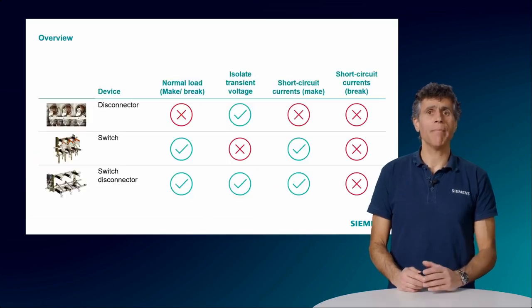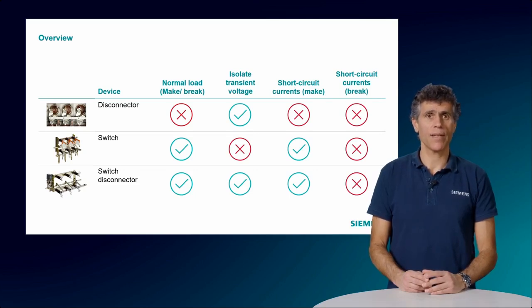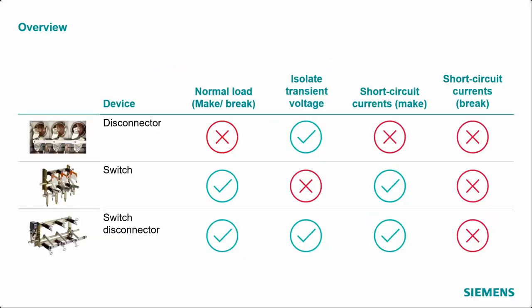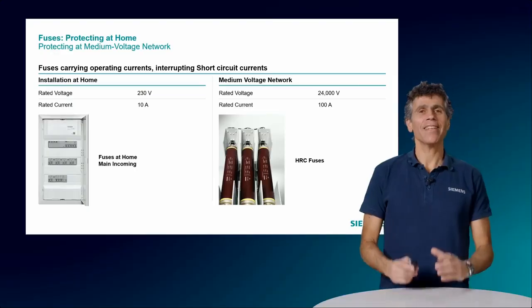And here, better than 1000 words, a short overview of the differences and common things on these three devices. As you see in the right column, none of them can break a short-circuit current. When we need that, we must use a circuit breaker. The switch disconnector is almost the sum of the switch and the disconnector, and that's maybe why we call it switch disconnector. And now the fuses.